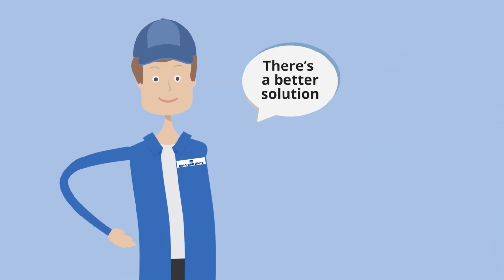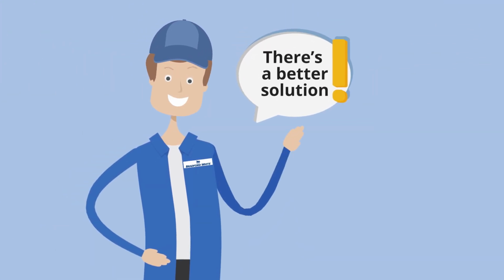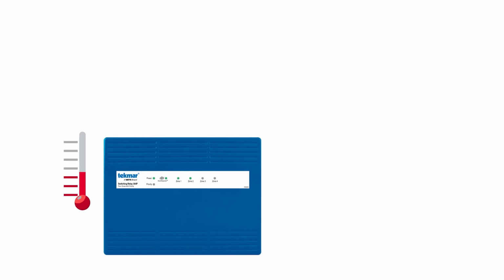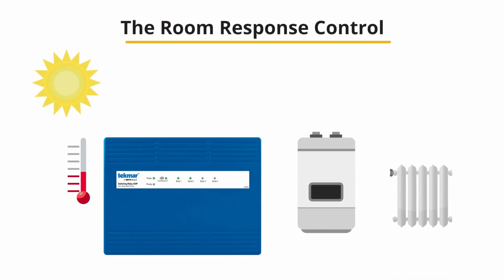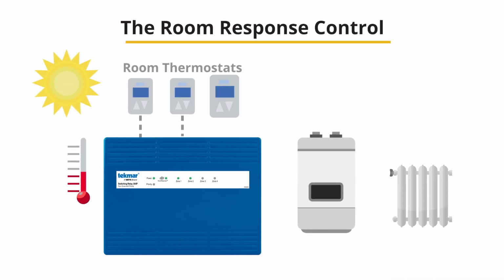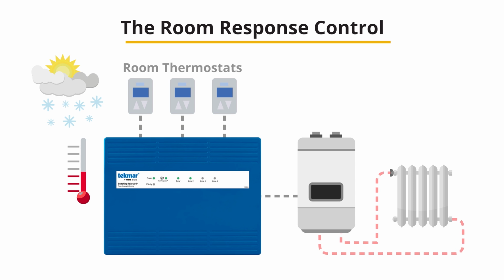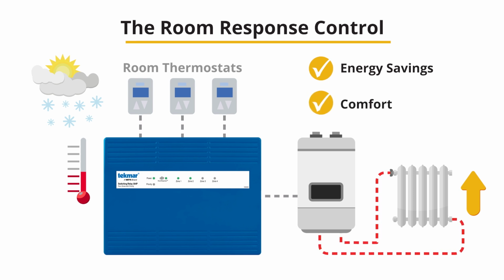Good news. There's a better solution to see how much heat your house needs. We use a control called the room response control that works with your current room thermostats. The room response control will send a message to your boiler telling how much heat is required and will then make adjustments to the burner flame to reach the perfect temperature. This maximizes energy savings without sacrificing comfort. Without a control like this, your boiler is working blindfolded.